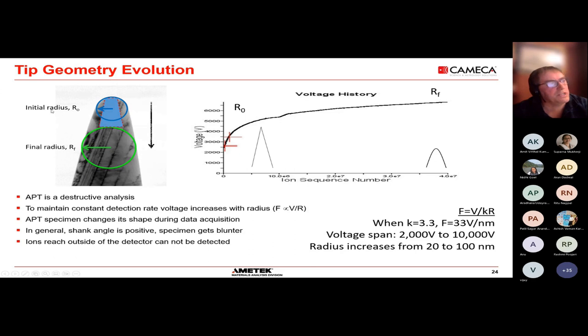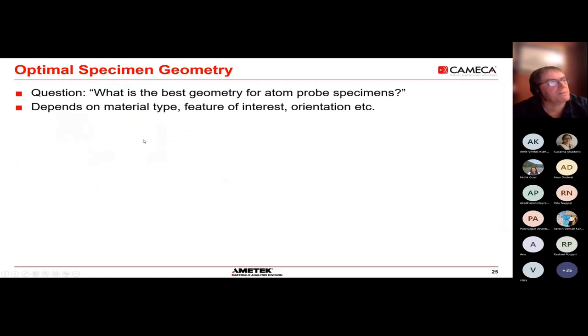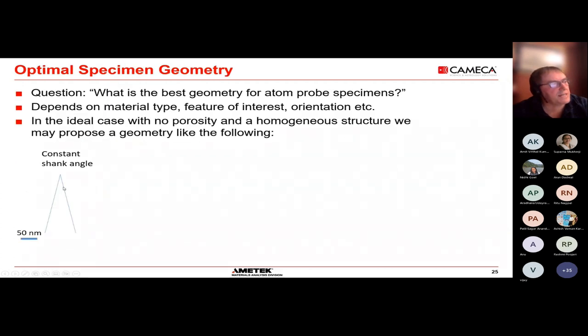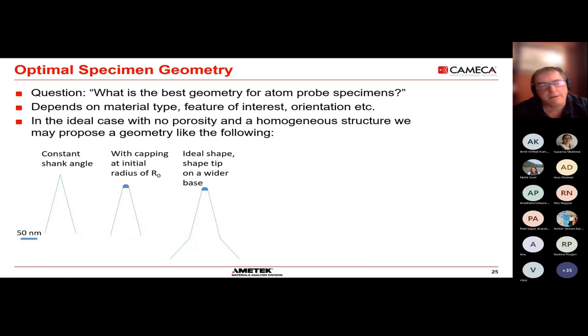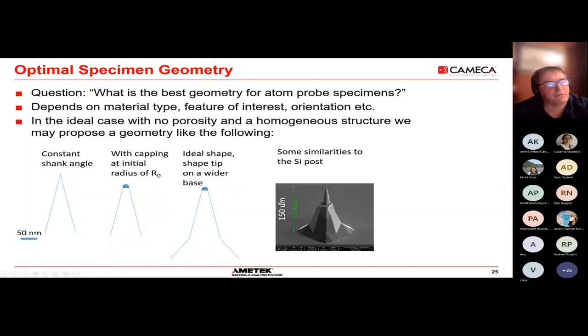The analyzed volume you achieve in your atom probe data reconstruction depends on the specimen geometry. If you have a constant shank angle, you don't want the specimen to be too long and thin because it becomes fragile. An ideal shape is thin at the top but thicker at the bottom — stronger. In our technology, we've developed micro-tips to mount and host specimens with these geometries.